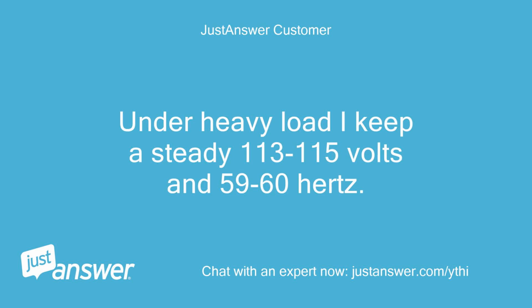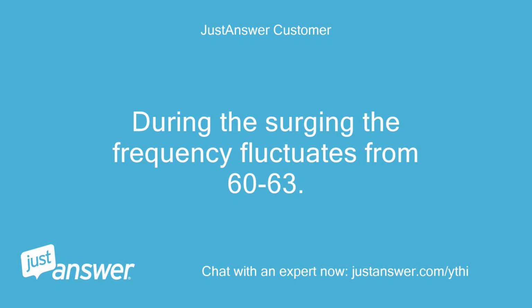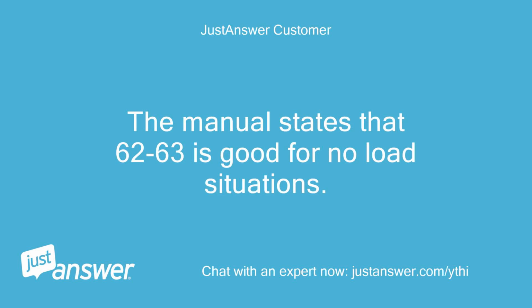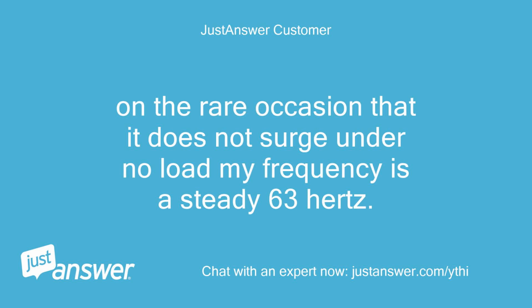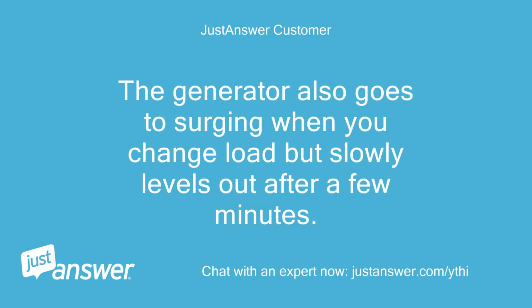Under heavy load I keep a steady 113 to 115 volts and 59 to 60 hertz. During the surging the frequency fluctuates from 60 to 63. The manual states that 62 to 63 is good for no load situations. On the rare occasion that it does not surge under no load my frequency is a steady 63 Hz. The generator also goes to surging when you change load but slowly levels out after a few minutes.